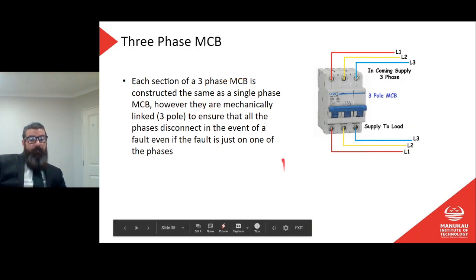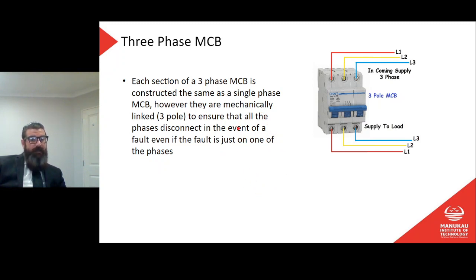Three-phase MCBs. Each section of a three-phase MCB is constructed the same as a single-phase MCB, however they are mechanically linked to three poles to ensure that all three phases disconnect in the event of a fault, even if the fault is only on one of the phases. That's important, right? If our MCB was constructed so that it would only trip if there was a high current on all three phases, then we could get a really big overload, get a short circuit on one of the phases, and it doesn't trip the others. So effectively, it's three separate breakers.